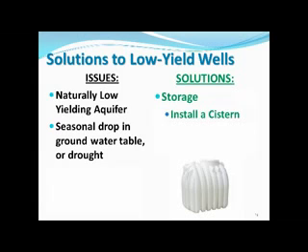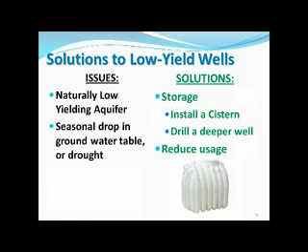You might also be able to reduce your short-term demands or spread it out during the day to allow storage within the well casing to recover better. Drilling a deeper or larger diameter well is another way to get more storage in your well, since your well casing can hold a lot of water. If the water level is seasonally dropping below the pump or has permanently dropped below it from drawdown, you will have to drill a deeper well.